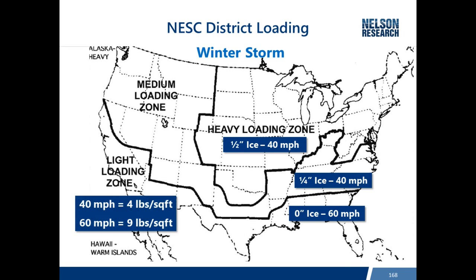For reference, a 40 mile-per-hour wind produces four pounds per square foot of area, while a 60 mile-per-hour wind produces nine pounds per square foot. As wind speed increases, force increases by the square of the speed — so even a 50 percent increase in wind speed, from 40 to 60 mph, equates to more than doubling the force on the poles.